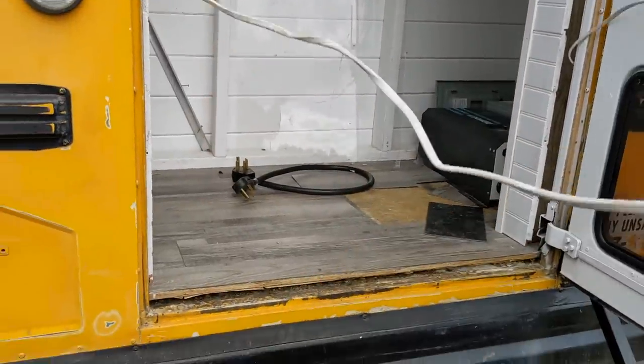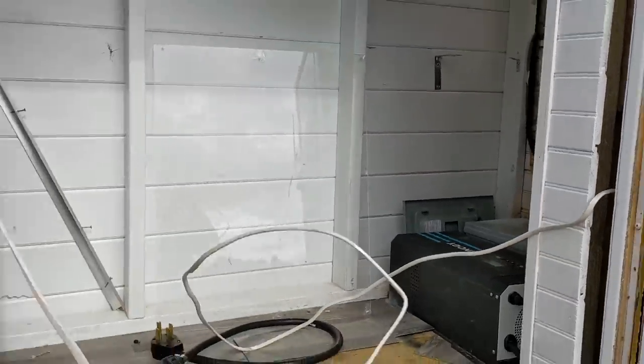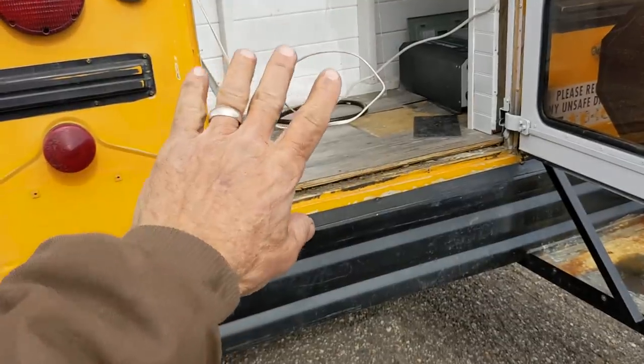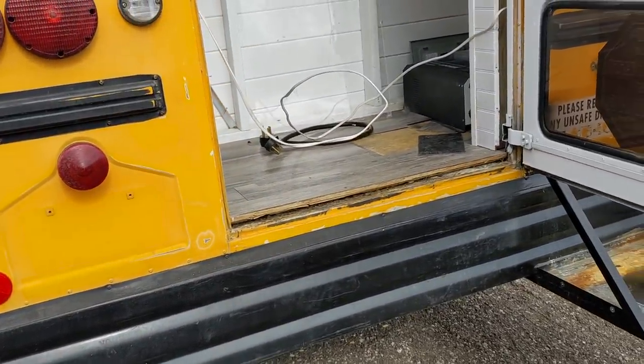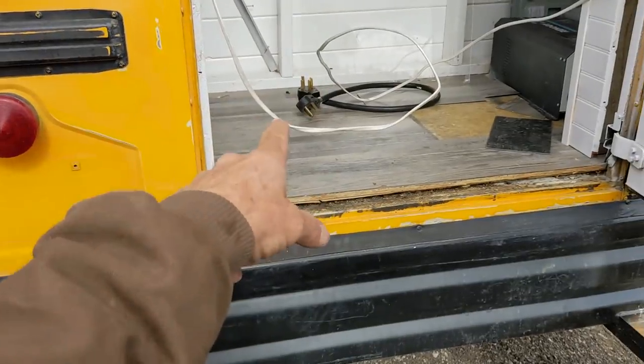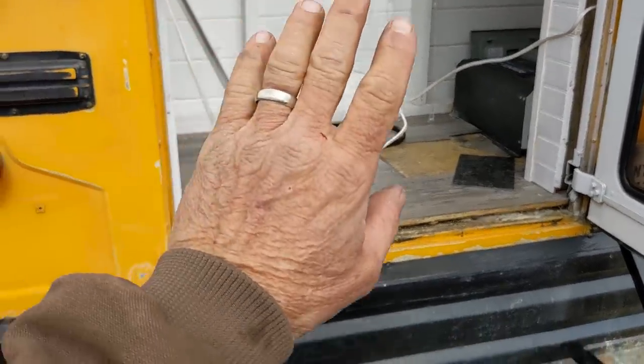You've got wires unsecured. They're going to get trapped. Sorry. This stuff just makes me angry. So they've got wires unsecured, the wrong kind of wire, the wrong size wire. They're using wire in wet locations that isn't rated for wet locations. They're giving customers things that are so dangerous that you can look them up under suicide cable and find a perfect example. So just stop, people. Stop doing electrical work.